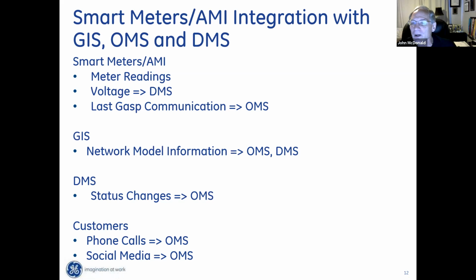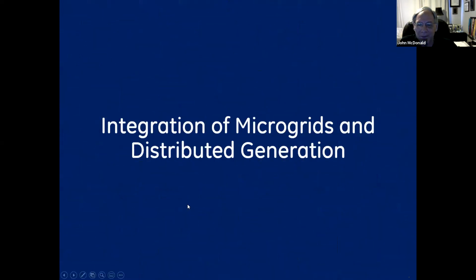When we're doing Volt/VAR control, we've got to make sure the voltage at the end of the feeder is within the limits for that country. In the US, the voltage at the customer must be 120 plus or minus 5%. So we've got to be careful. We can't be too low voltage at the end of the feeder. The geographic information system is the reference system for the network model. And then with customers, I mentioned we want to move from phone calls to social media.